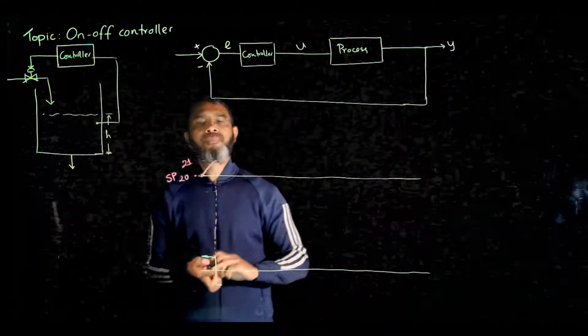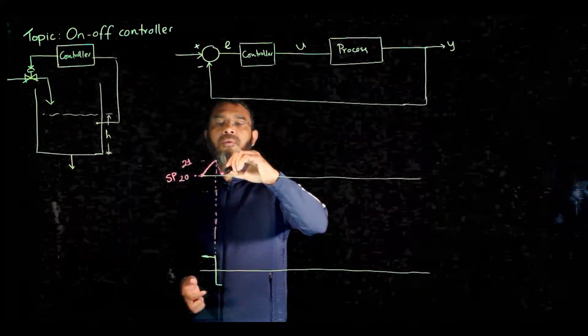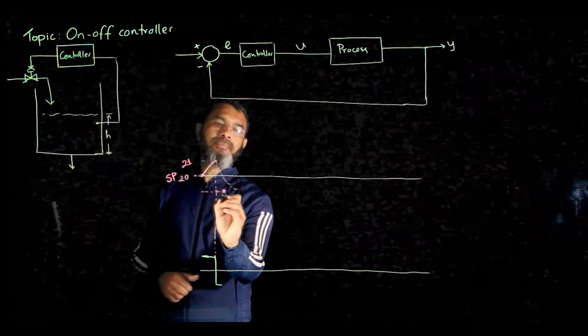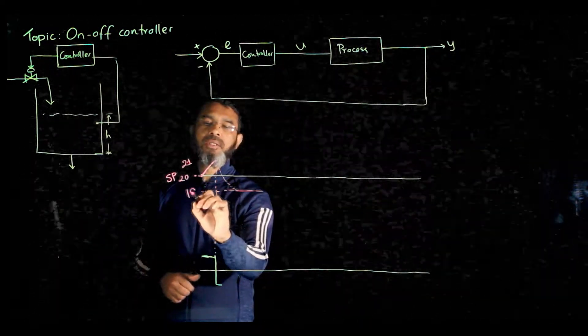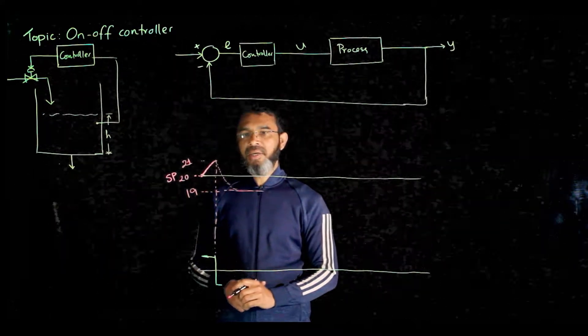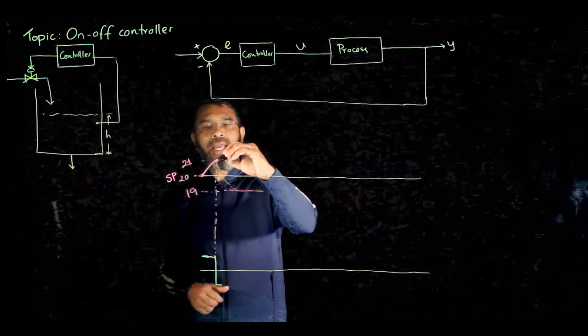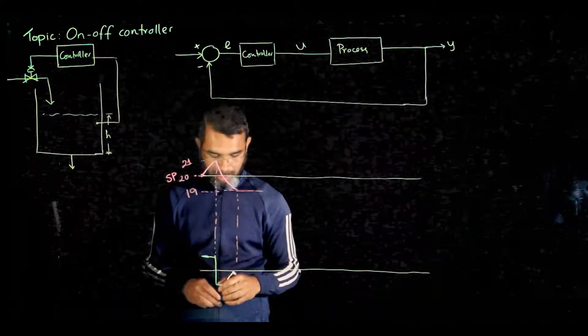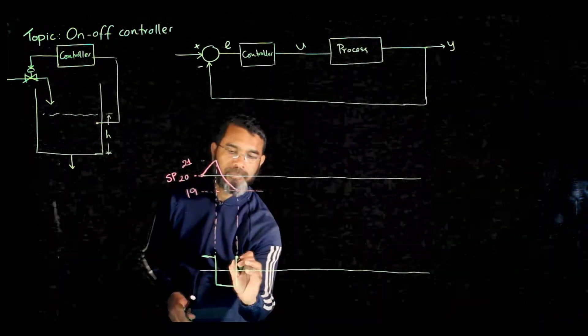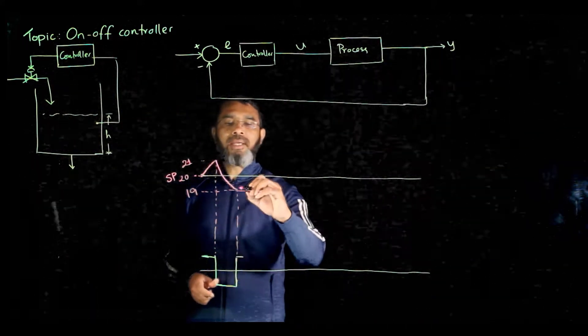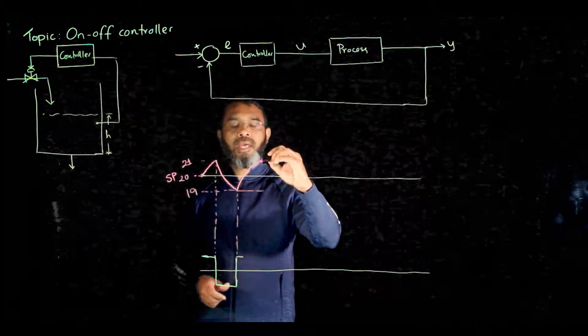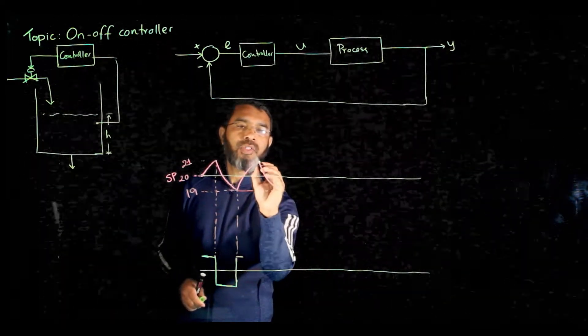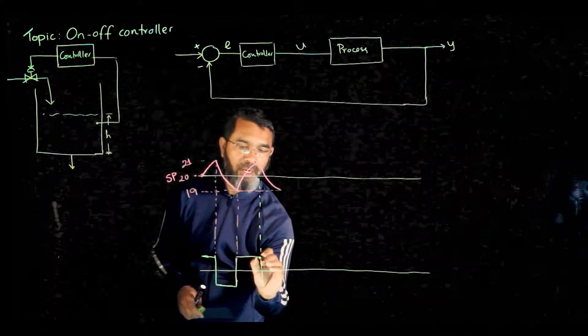Now when the level starts to drop, at what point do you want the valve to turn on again? Suppose you have a tolerance level here, so when it goes to 19 you want the valve to turn on again. So the level comes here and at this point you want the valve to turn on again. So the valve will turn on, and when it turns on the level will go up again, and it will come down. So it has some oscillation in the level itself - the valve will keep on turning on and turning off.